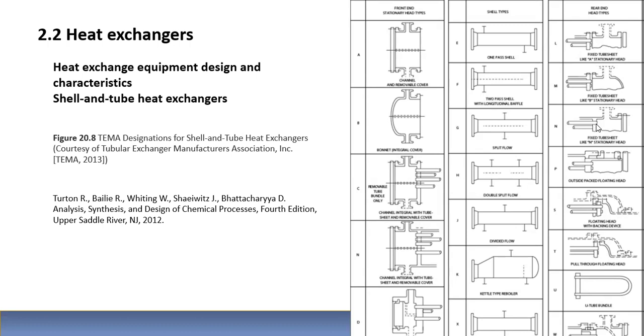Este espejo es donde se sueldan los cuellos de estos tubos, y al otro lado, que es el cabezal de ingreso, usted ve también el espejo y ve los tubos soldados en el espejo. Aquí se encuentran soldados los tubos en el espejo. Acá también, soldados en el espejo. Entonces, de un lado, a través de la carcasa, el interior de la carcasa, llega al otro espejo, el tubo por donde interiormente va a fluir el fluido de proceso. Afuera de los tubos, del lado de la carcasa, va a fluir el fluido que corresponde en la parte exterior.